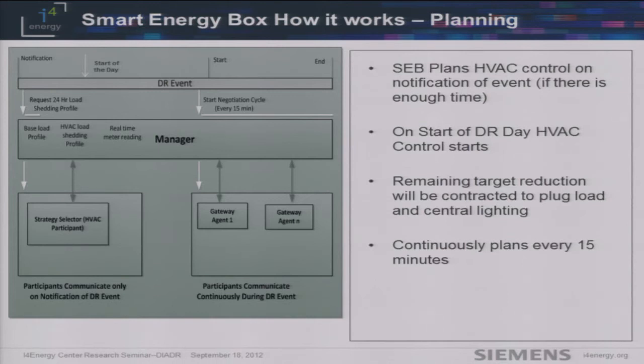Central lighting can be turned off and you can immediately see the load shedding. We also have distributed load control where we can contract load shedding throughout the building — agents can control laptops, lighting, or any equipment not centrally controlled. We adapted an adaptive approach where it communicates every 15 minutes and tries to achieve as much of the target as possible.